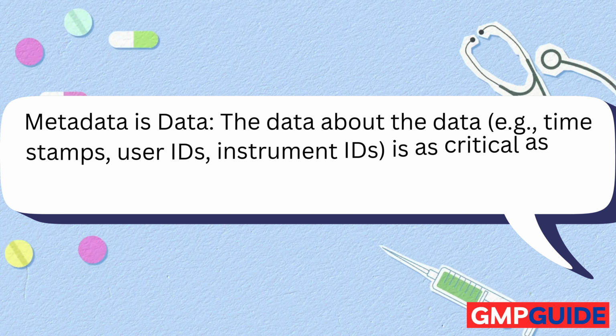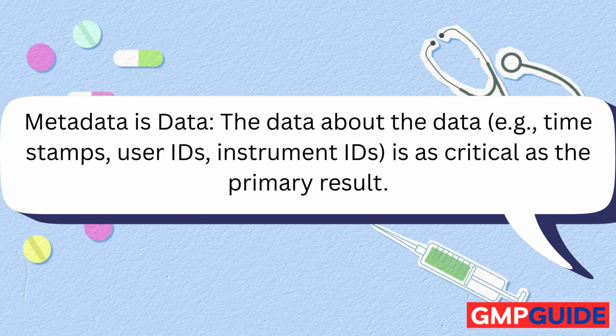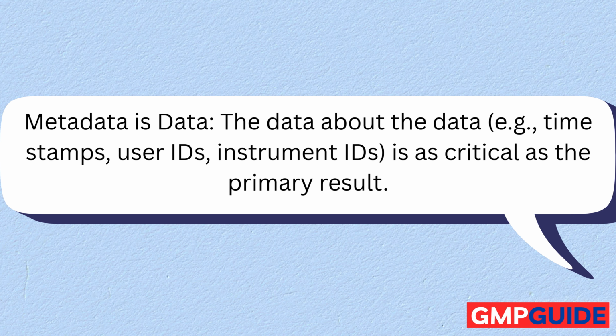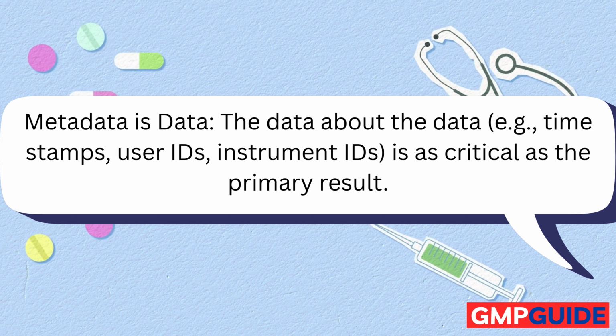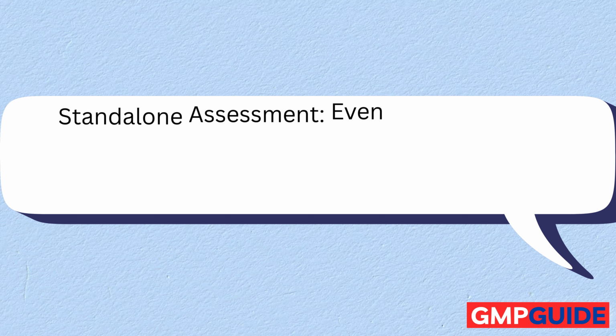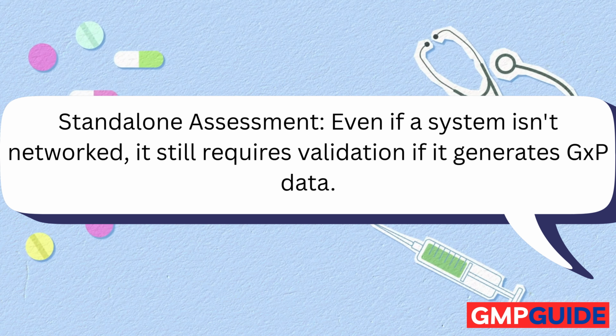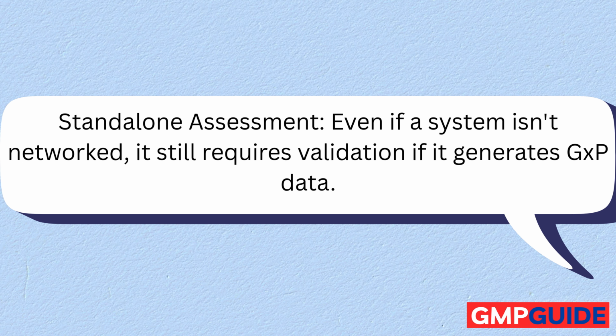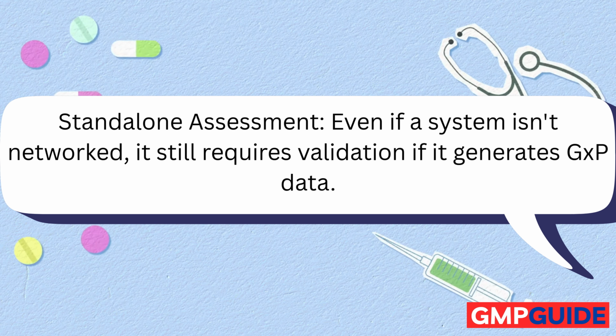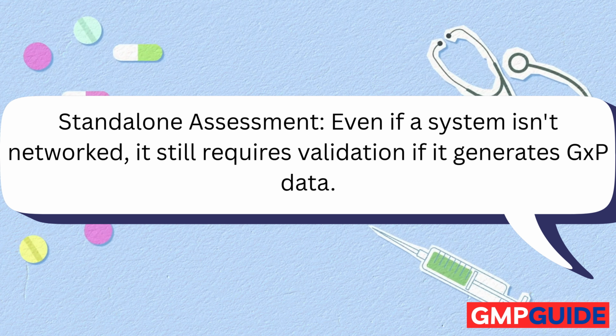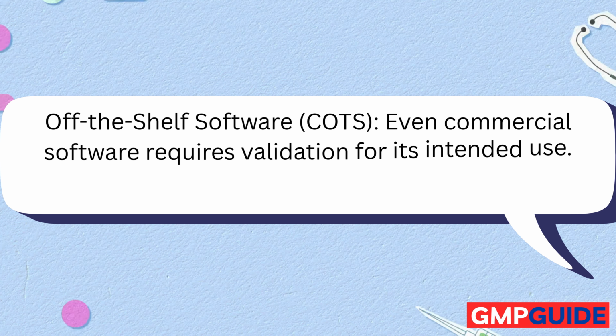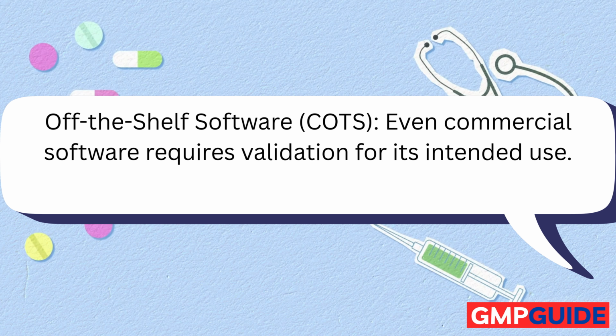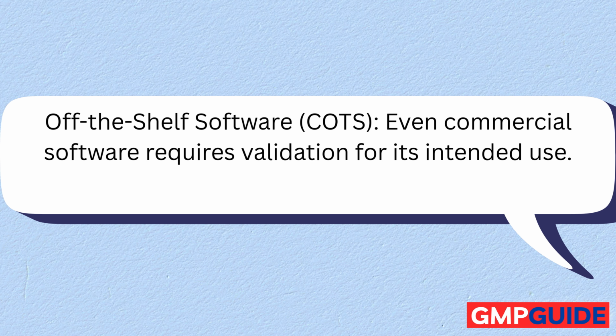Metadata is data. The data about the data, e.g., timestamps, user IDs, instrument IDs, is as critical as the primary result. Standalone assessment. Even if a system isn't networked, it still requires validation if it generates GXP data. Off-the-shelf software, COTS. Even commercial software requires validation for its intended use.